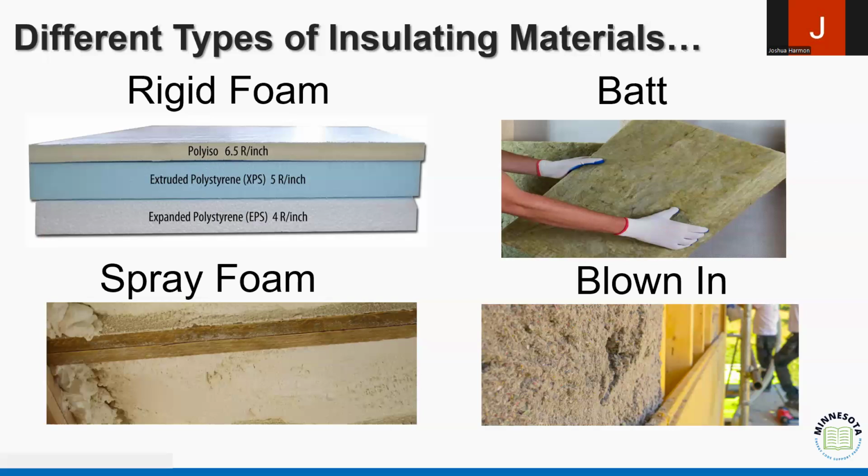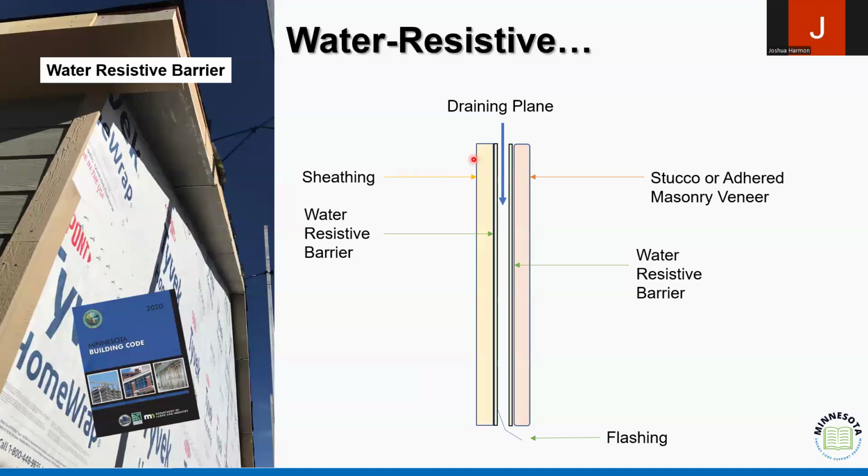And what we're looking for is, again, let me jump back to this, right? We're trying to create that weather resistant barrier that exists both on the exterior wall as well as the interior wall, on the warm side. On the exterior, we've got our stucco. I don't have a great image, but we'll try and visualize. So this is our exterior design, right? We've got some kind of exterior cladding. We've got some level of water resistant barrier so that if moisture does penetrate in, we've got a drainage plane that allows it, through flashing, to get away from the building, right?